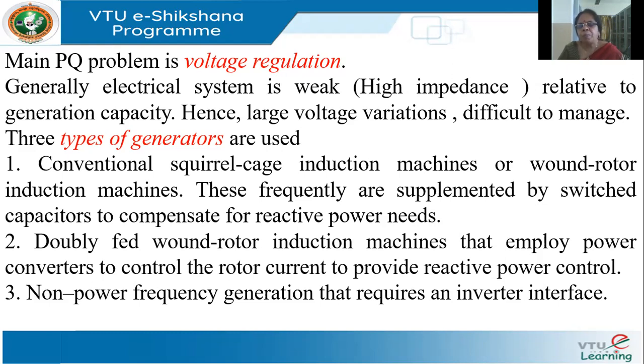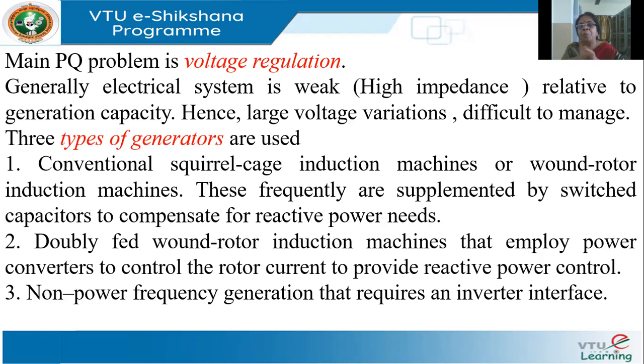With wind turbines, the main power quality issue is voltage regulation — that is, changes in voltage as the load varies. Wind farms are located remotely and connected to the grid with no other connections nearby, so the impedance will be high. When impedance is high, even small changes in current lead to large voltage drops (V = I × X), causing large variations in voltage. This is one of the main power quality problems, and wind farms must take care of it by improving voltage regulation.